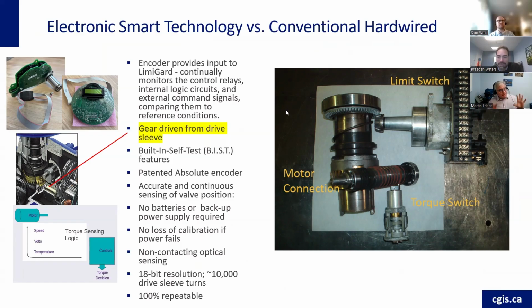From this slide, I just want you to see the difference in the technology. The conventional technology has a switch. There's a bunch of gears here that turn and turn, and a bevel gear arrangement. The torque switch is also mechanical, you can see it's an offset arm, and when this slides back and forth, it trips the torque switch. That's the core, the heart of the conventional actuator.